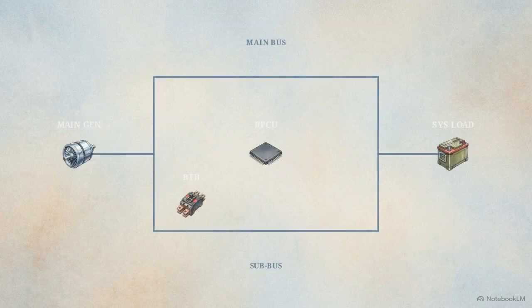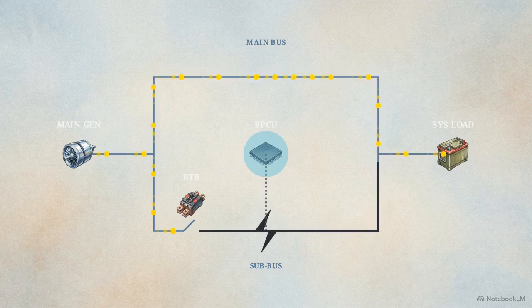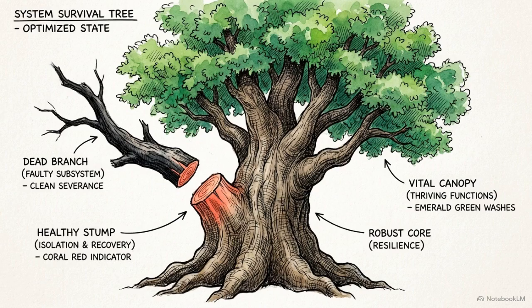If a short circuit flashes across a subbus, the system reacts in milliseconds. The BPCU detects the massive spike and fires the adjacent bus tie breaker open. That subbus drops offline, but the rest of the electrical grid reroutes around the dead zone, operating normally. When catastrophic, localized damage occurs inside an electrical grid, physical isolation is vastly superior to synchronization. By cutting off the infected branch, the core system survives.